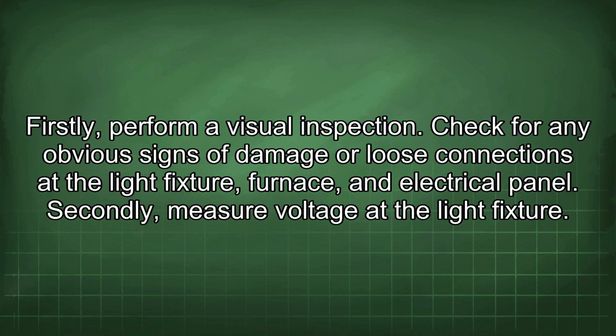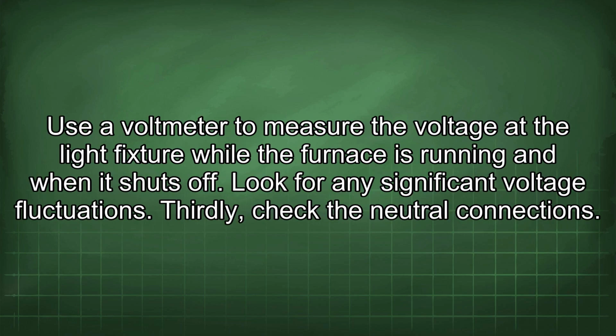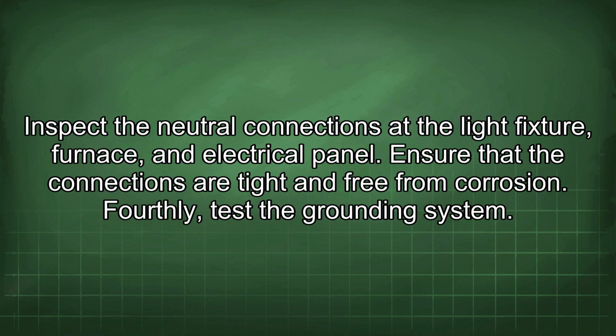Firstly, perform a visual inspection. Check for any obvious signs of damage or loose connections at the light fixture, furnace, and electrical panel. Secondly, measure voltage at the light fixture. Use a voltmeter to measure the voltage at the light fixture while the furnace is running and when it shuts off. Look for any significant voltage fluctuations. Thirdly, check the neutral connections. Inspect the neutral connections at the light fixture, furnace, and electrical panel. Ensure that the connections are tight and free from corrosion.